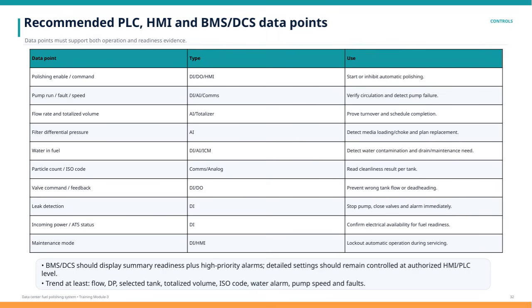Monitoring the pump status, whether it's running, faulted, or its speed, helps verify circulation and quickly identify any failures that could disrupt the process. Flow rate and totalized volume readings are crucial because they prove turnover and help schedule when the polishing should be complete. Filter differential pressure measurements alert us to media clogging or the need to replace filters before the system's efficiency drops. Detecting water contamination in fuel is vital. We're looking for that via digital and analog inputs, which can trigger necessary maintenance actions like draining.